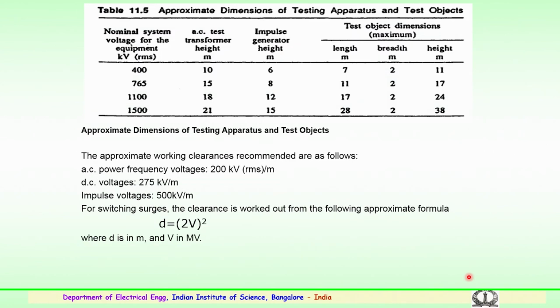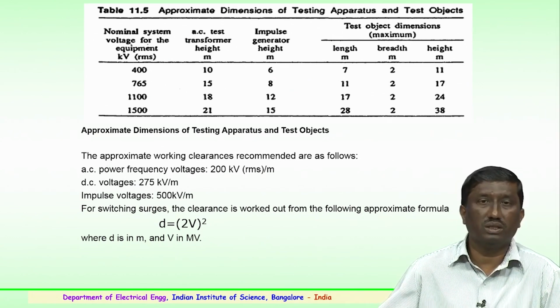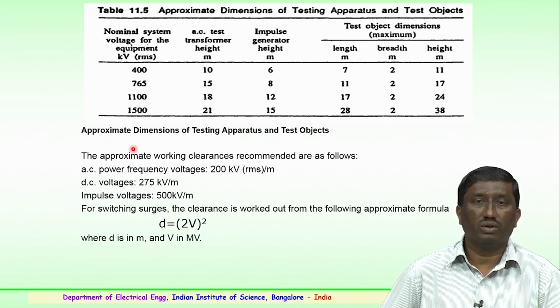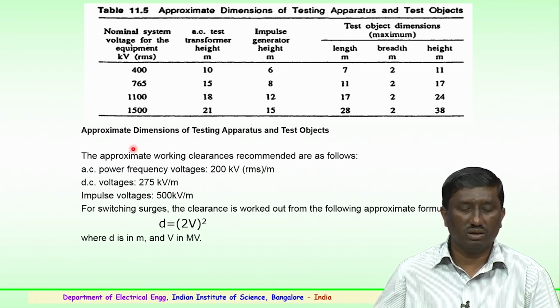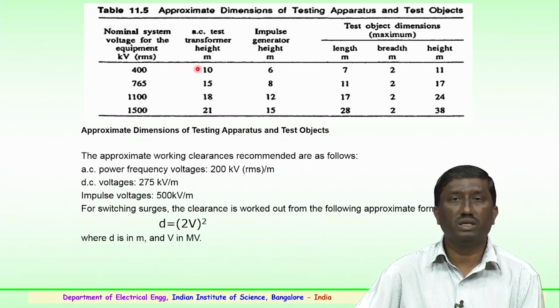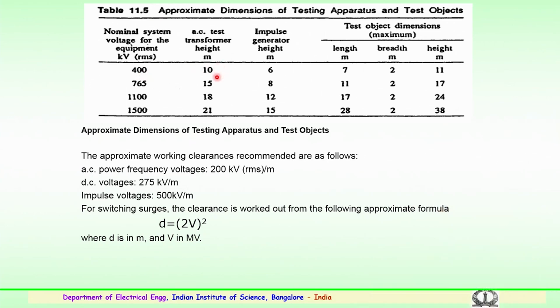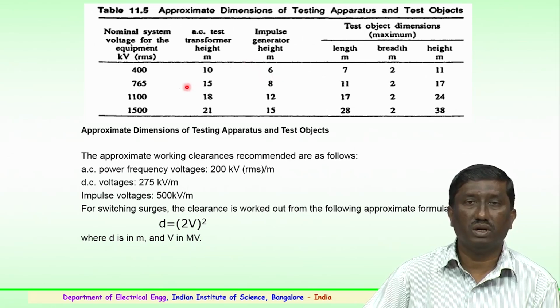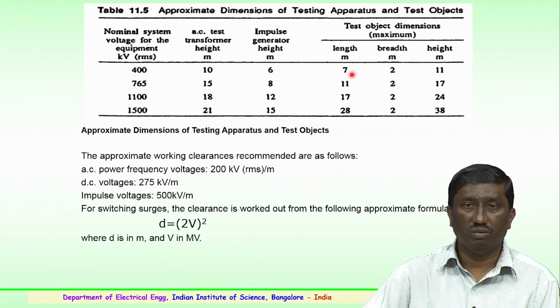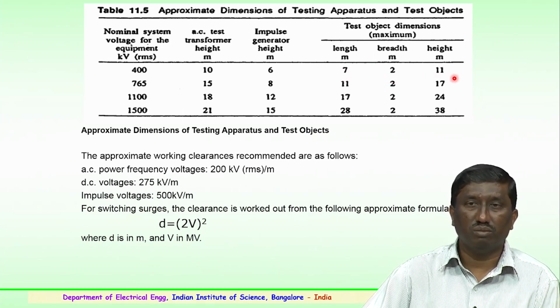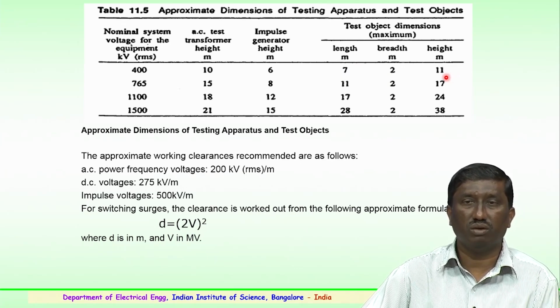The table gives the approximate dimensions for testing apparatus and test objects. Here you can see the nominal system voltage for the equipment in kV RMS. For a 400 kV system, the AC test transformer height could be around 10 meters, and the impulse generator height could be around 6 meters. The test object, the equipment to be tested, could be 7 meters in length, 2 meters in breadth, and 11 meters in height. This has to be kept in mind before planning high voltage laboratories.